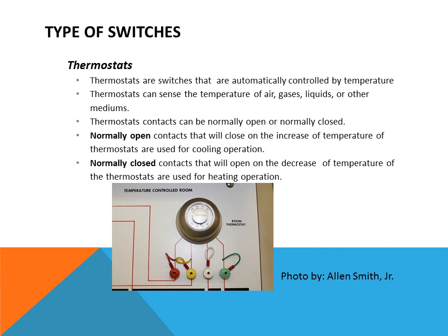Normally open contacts that will close on an increase of temperature are used for cooling systems, and normally closed contacts that will open on a decrease of temperature are used for heating apparatuses.